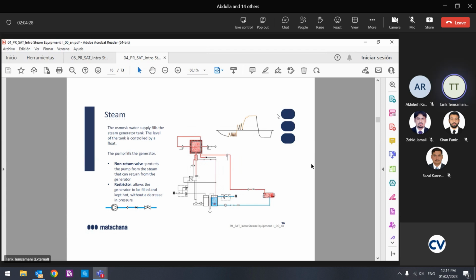But there is another question. Maybe everything is okay, but I don't reach the pressure. If I have a leak, it can be a reason. I have a leak in the chamber. Yes, a possibility, in the door or in the gasket, like that. So I am putting steam here, but it's not retained.